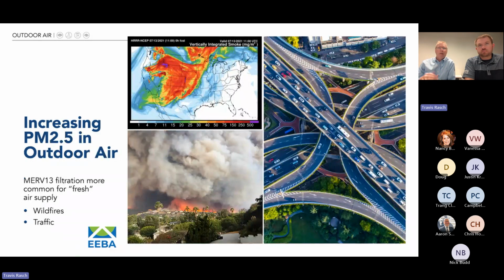I mentioned PM 2.5. It's everywhere, comes a lot from cooking also. But one thing, we like to assume that outdoor air is fresh air. But with all the wildfires we've had the last 5-10 years, outdoor air isn't always fresh air. So as evidence of that, as an example, California now requires MERV 13 filtration, which is going to catch almost all that PM 2.5 from wildfires. They require that on any incoming air. So if you have a supply fan system or HRV with incoming air, you need MERV 13 filtration on that. So something to keep in mind that may be a trend that's going to sweep across the country. And I know ASHRAE 62.2 is talking about increasing filtration requirements as well.